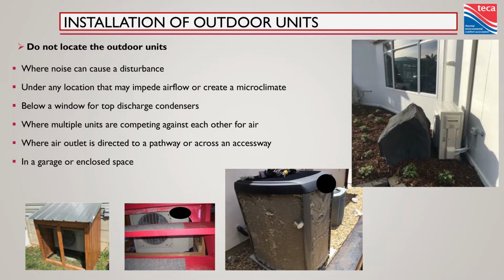But a real key thing is to make sure there's no obstruction in front of the discharge, whether that's a side discharge heat pump or a top discharge heat pump, free and clear of anything that's going to impede airflow. So, you know, they're kind of unsightly, but don't put a decorative rock in front of it. That's a side discharge heat pump. That thing has no chance of doing its job. You want to protect it from snow, but I don't know any fridge mechanics that are going to be able to get at the compressor on that thing. So maybe it needs some hinges. The air is going to come out of that, but I don't know how it's getting into the backside of that coil. That would not be a heat pump that I'd say has free area in front of it.